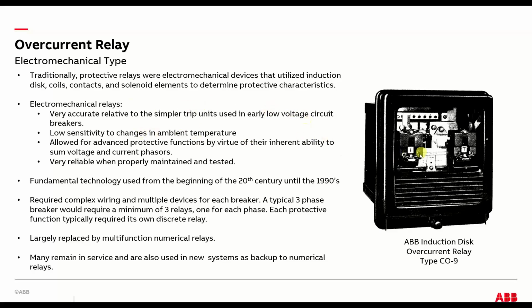The electromechanical relays are kind of clockwork-like devices, and they tended to be in the medium voltage world because they were more accurate, and there were more things you could do with them in terms of protection as opposed to stuff that was in utilization equipment at low voltage. The electromechanical used induction discs and solenoids and things like that to achieve the protective function, whereas the circuit breaker at low voltage used thermal heaters or just thermal elements plus some magnetic stuff. But that was sort of the origins of it.